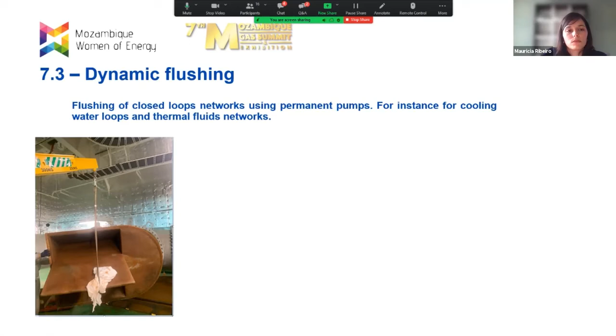Here we can see in the picture the filter of this cooling water system. For this flushing, basically what we do is fill up the system with water, and it will run continuously with the permanent pumps. As soon as the strainers are plugged, we stop the pumps and clean the strainers. That's what we do in dynamic flushing, we call it that since we use the permanent pumps.